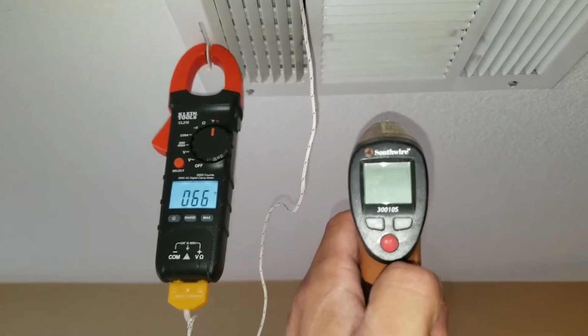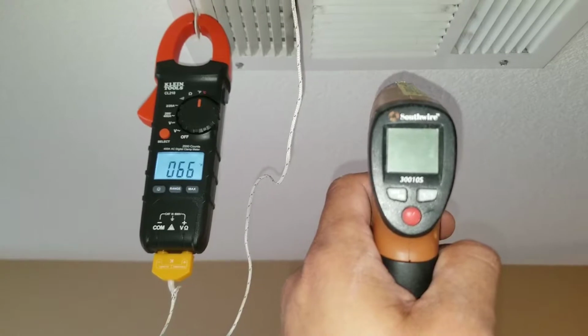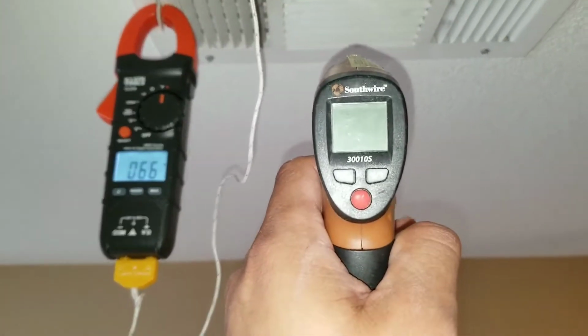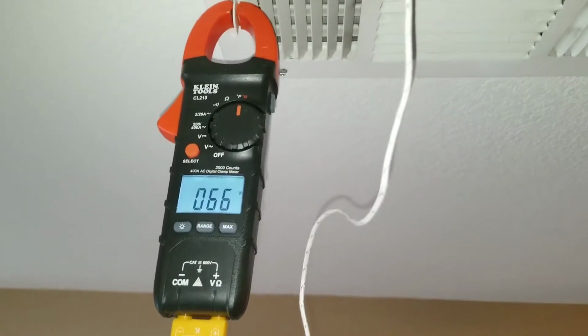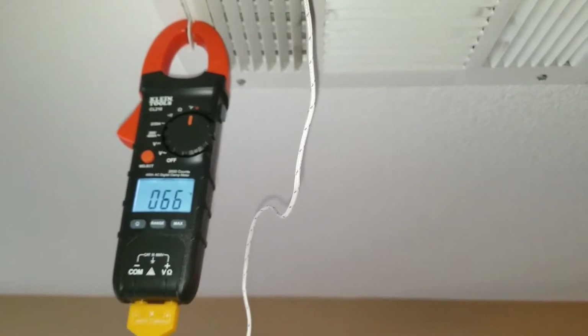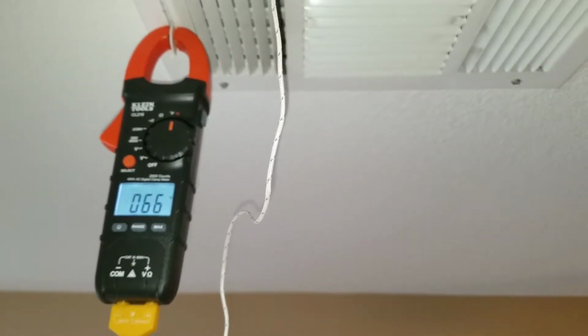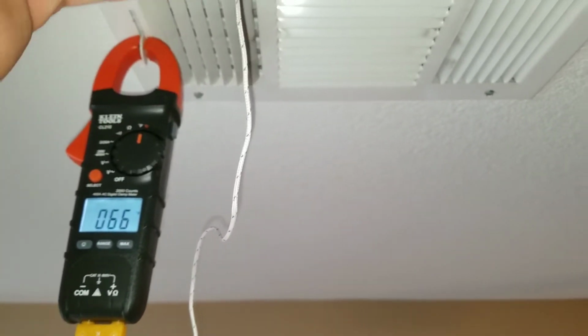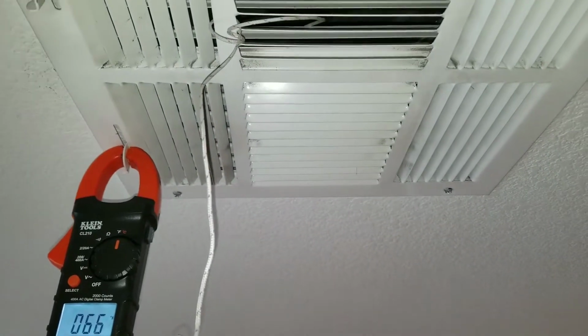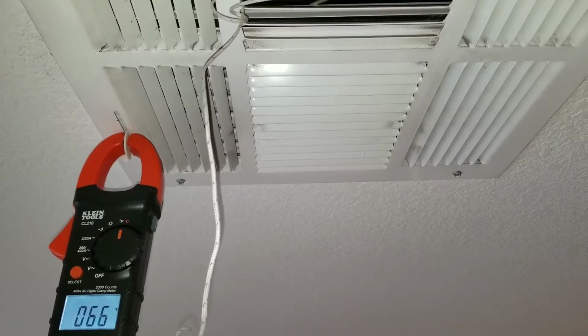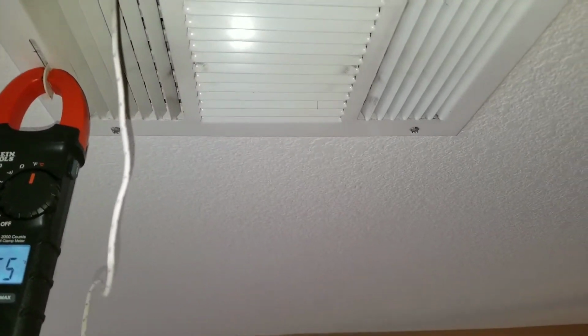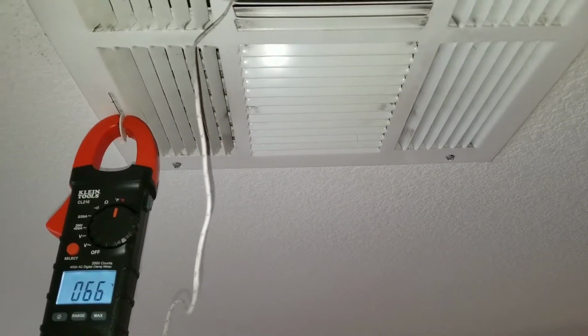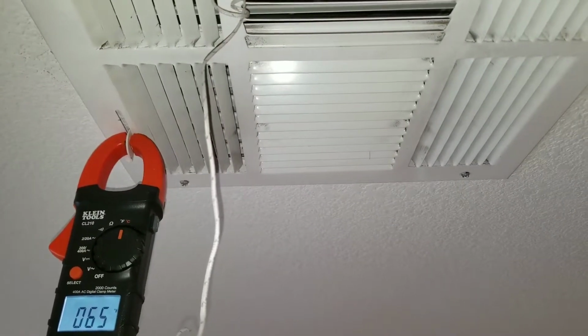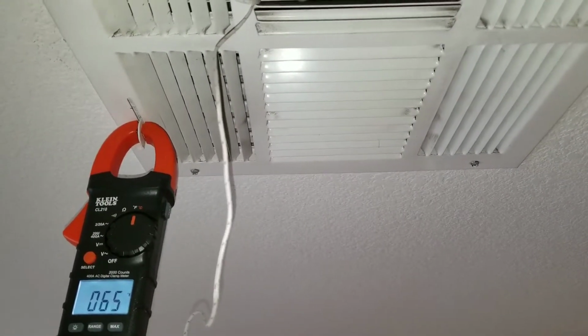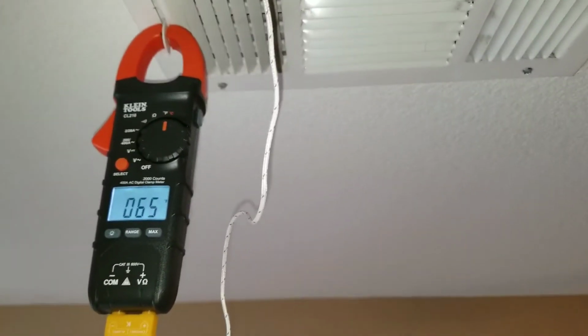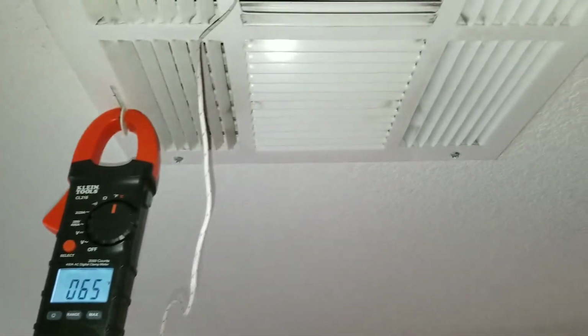The reason this is important to note is because if you do get an AC call where the unit or the house has been vacant, especially when you're dealing with houses that have the ductwork running in the attic, such as your furnaces, you're going to want to take into account when you're taking your reading that you want the reading of the actual air temperature coming out of your vent. If the house has been vacant, it's the middle of the summer, and you're trying to take a temperature reading using your temp gun, there's going to be a significant difference, because it's going to take a few hours for that vent to actually start to cool off before it drops to a proper reading.